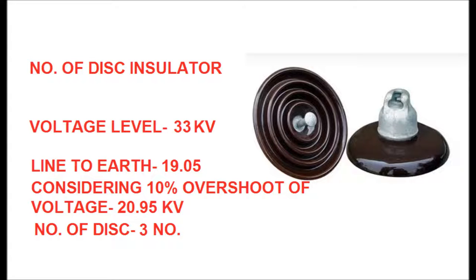For the 33 kV voltage level, the line-to-line voltage is 33 kV and the line-to-earth voltage is 33 divided by √3, which equals 19.05 kV. Considering a 10% overvoltage, that comes to 19.05 × 1.1 = 20.95 kV. Dividing 20.95 by 11 gives approximately 2. For safety, one additional disc is added, giving 3 discs for suspension type and 4 discs for tension type string in a 33 kV system.